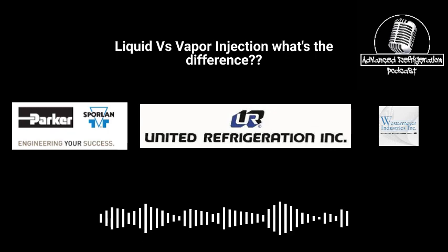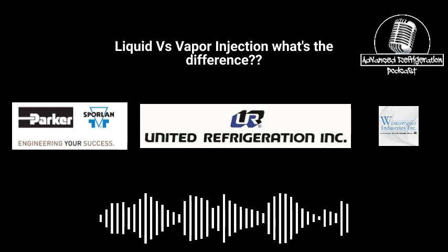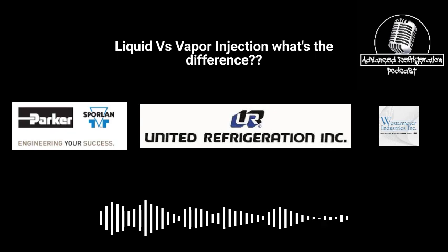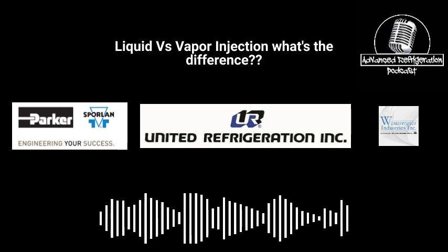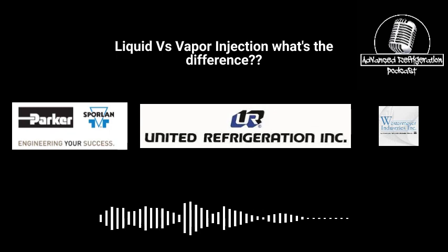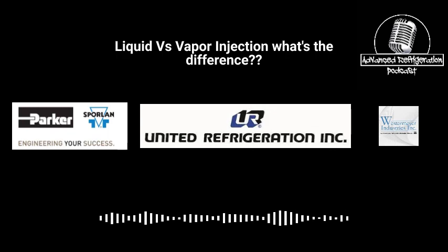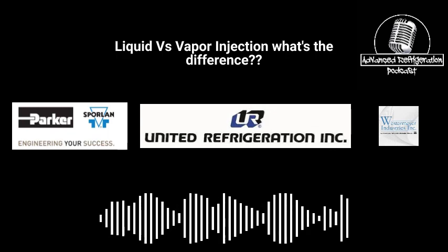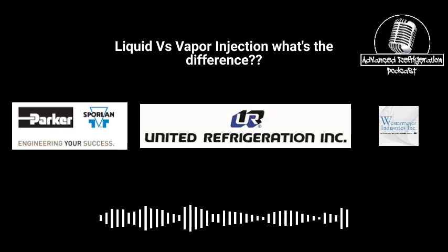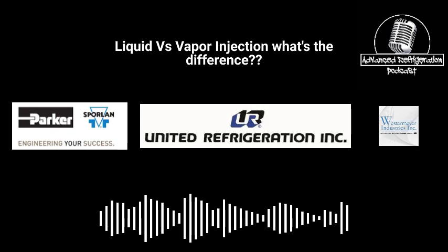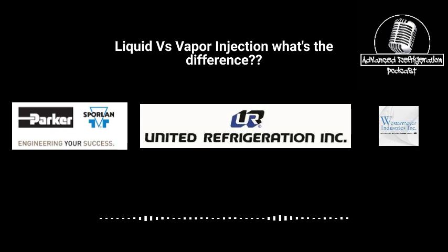But yeah, I'm not infallible. I screw up, and I probably spent a good 25, 30 minutes diagnosing this thing, making sure there were no shorts in the wire, no weird resistances, and that the pressure transducer was putting out the right voltage for that pressure. I went the whole night. I'm like, well, it must be the control. Well, yeah, it was, asshole. I didn't have it programmed right. But I was like, this controller has been in this rack since 2005. Why all of a sudden would it be reading wrong now? Well, because it's been reading wrong forever, apparently.